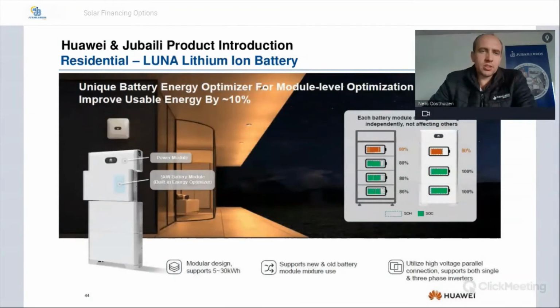Then on the residential side, Huawei has got its own battery system. It's called the Luna. It's a lithium-ion battery. The advantage of this battery system is that each battery will be controlled individually, and an older battery or a battery that might not be as good as a newer one will not affect overall performance. So if one battery might be performing at 80%, the other two can still remain on 100%.